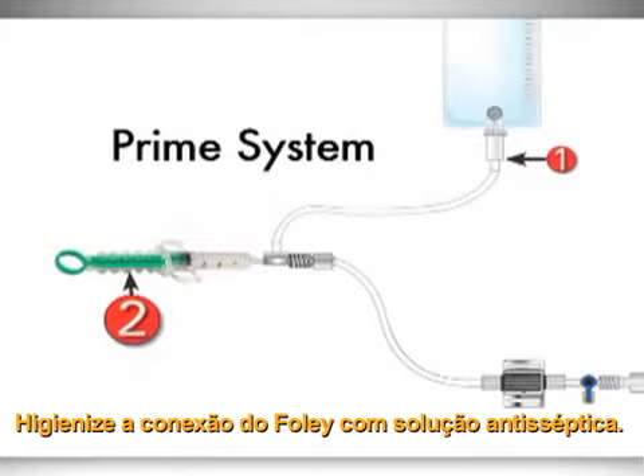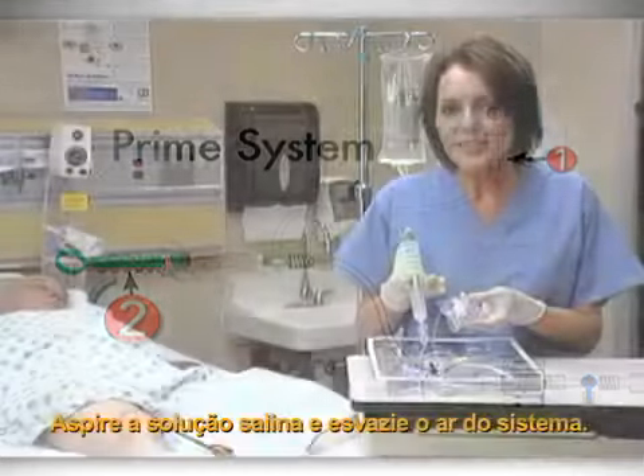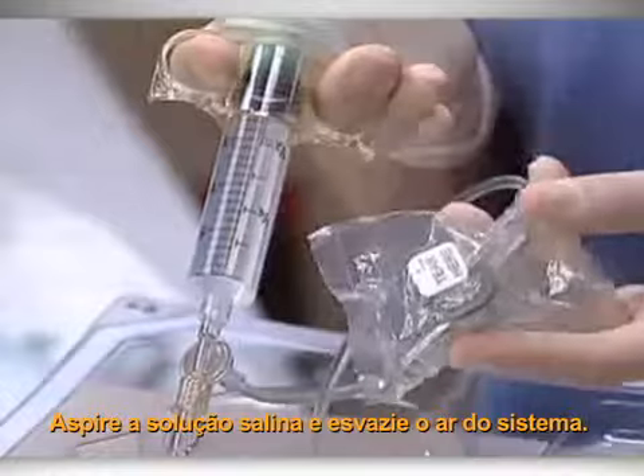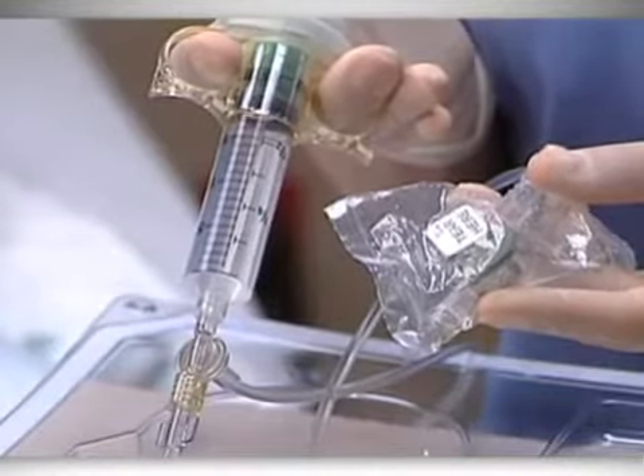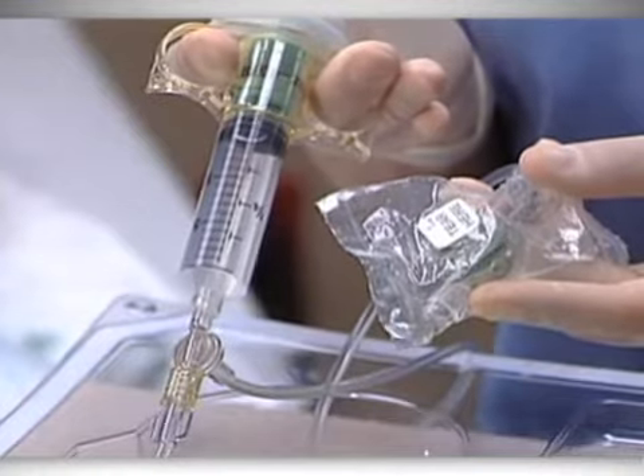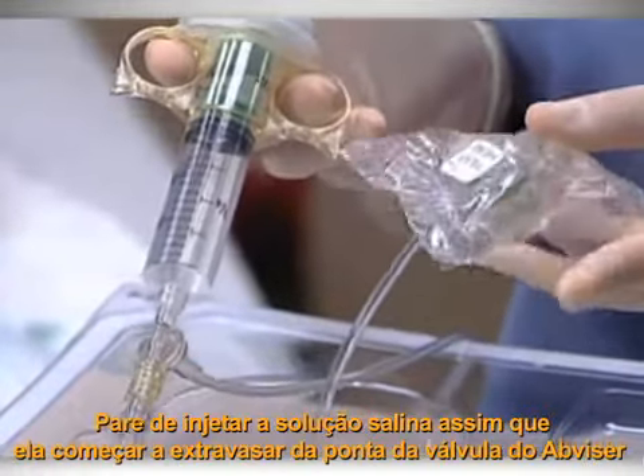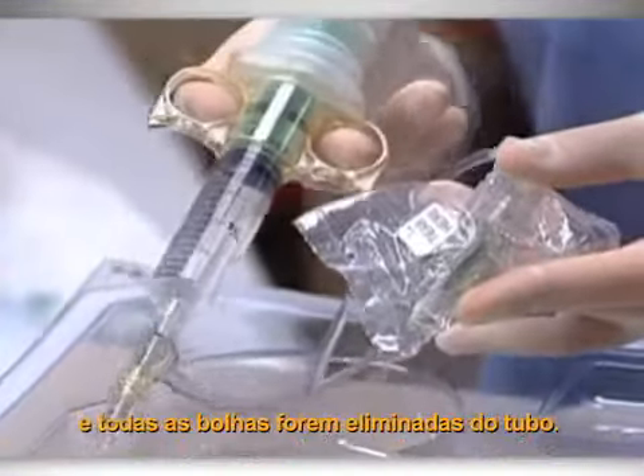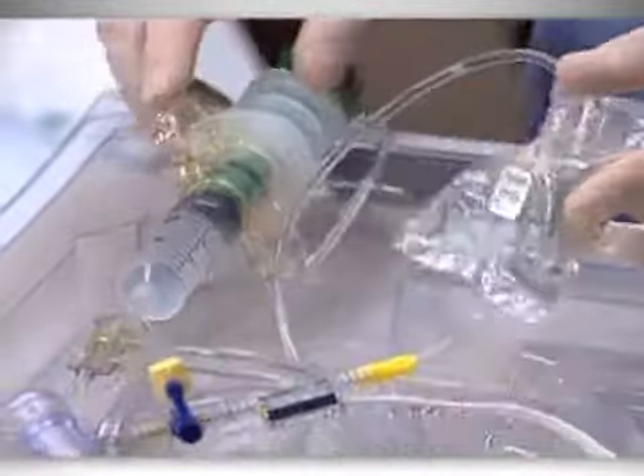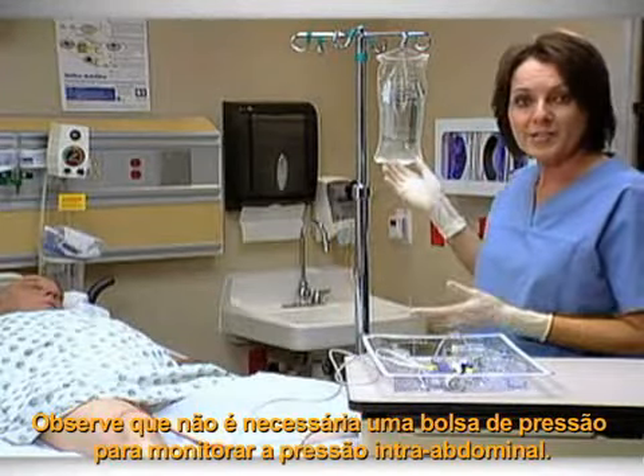Prep the Foley connection with antiseptic solution. Aspirate saline and flush air from the system. Stop injecting saline once it is running out of the tip of the Abviser valve and all the bubbles are cleared from the tubing. Notice that no pressure bag is required for intra-abdominal pressure monitoring.